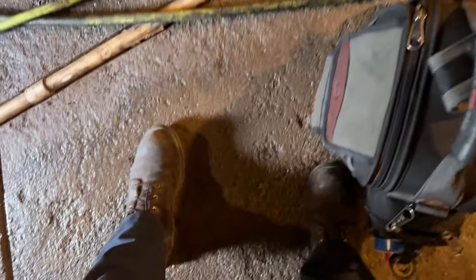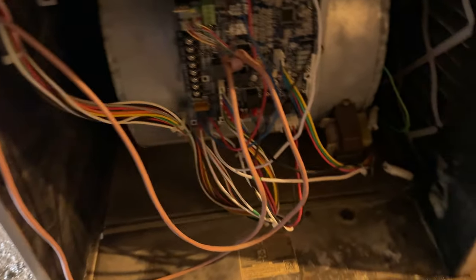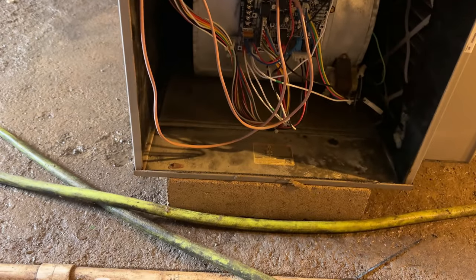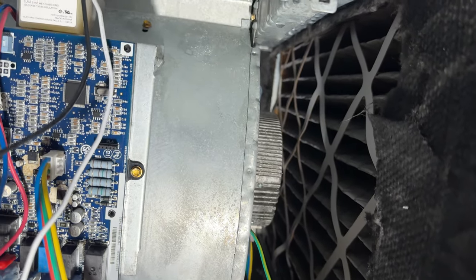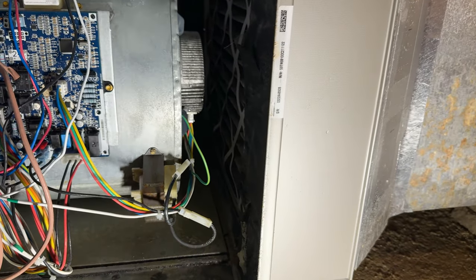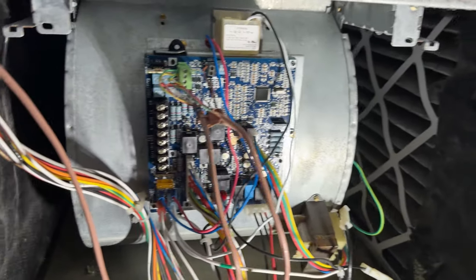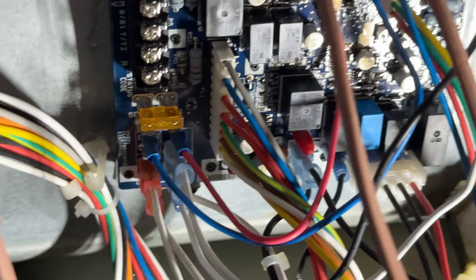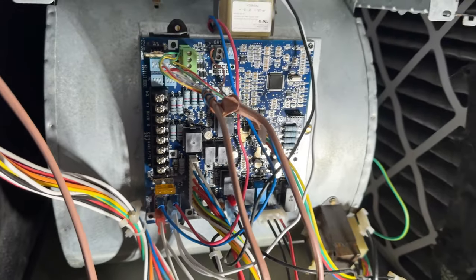He said the motor had some water in it — yeah, we may be having some issues here. Technically it's four o'clock. What a hot mess. Can you believe somebody actually put it down here? Basically what we got going on here is they did not have the whole motor — so all they have is the end controller. The fuse was blown, and he ended up only having a five amp. So he put that in there. We'll switch that to three when we get done.